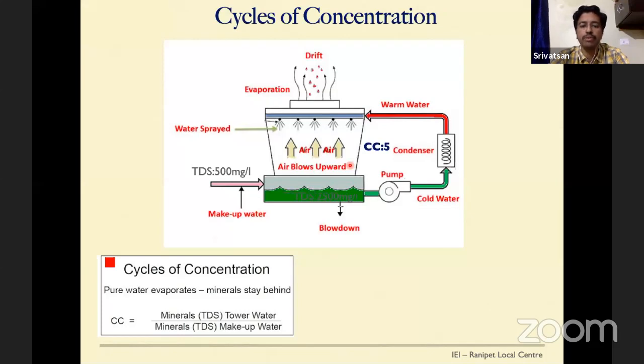So whatever water we need to blow down will be at 2500 milligrams per liter. If we don't blow down some water, this concentration keeps on increasing. Since we have a constant inlet water TDS of 500 milligrams per liter, we need to blow down a certain volume of water so that we maintain the concentration here at 2500 milligrams per liter. If the concentration increases here, the condenser tubes and piping will get corroded. So basically, we use copper as the condenser tube material. Then if it's a higher cycle of concentration, we go for SS304 or higher, SS316L.